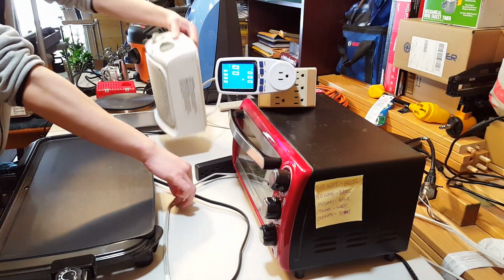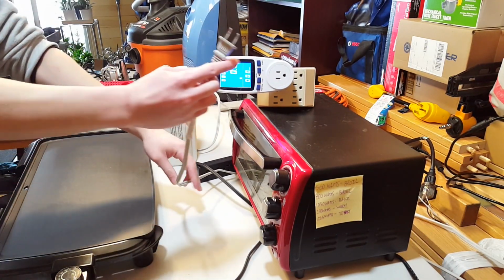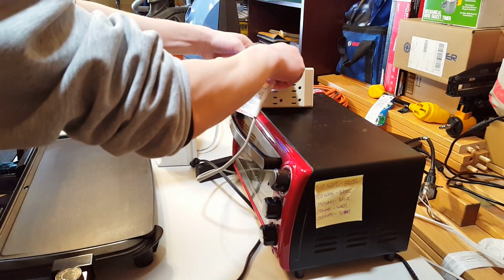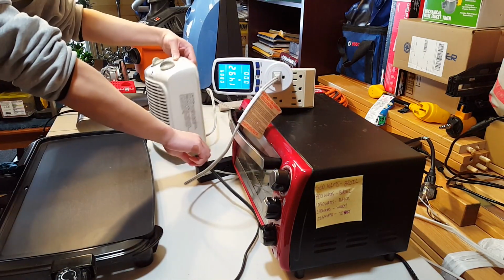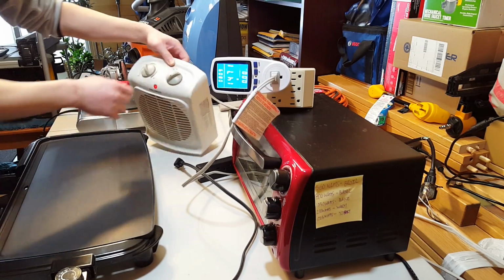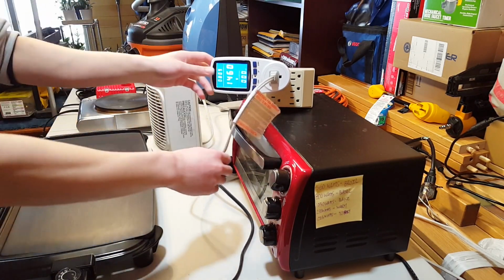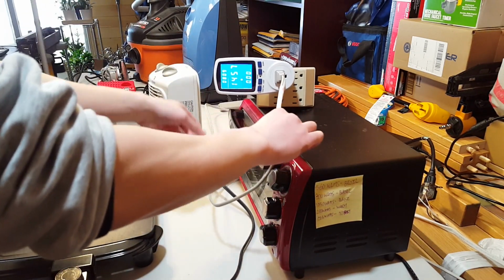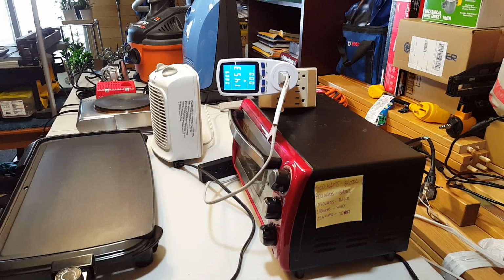1500 watt space heater. There's 3 different settings. Actually, there's 4. There's a fan only, a low, a medium, and a high. So right now we're on the high setting for 1500. It's close to 1500. This is still in battery mode. It's doing 1453. Check AC amps. 12.69. BMS software says 30 amps.